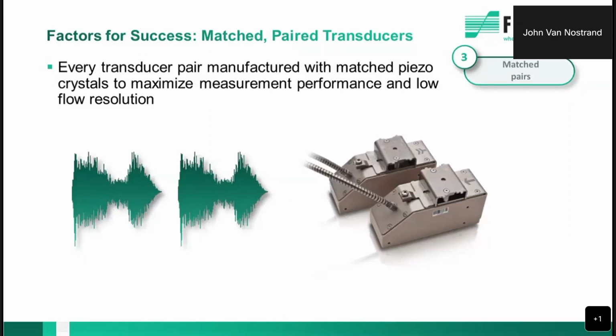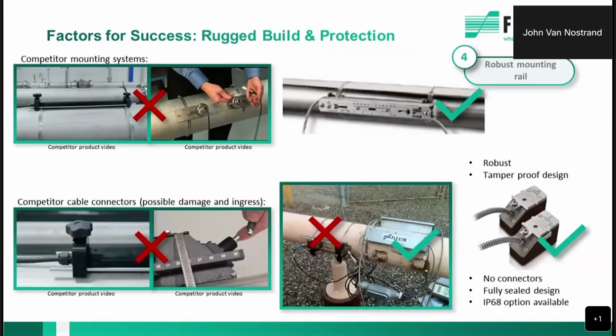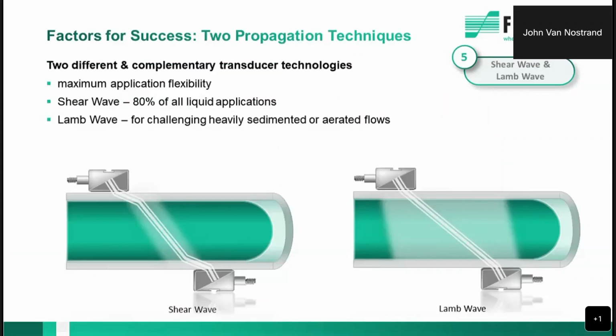I mentioned we match the piezoelectric crystals, and this provides us the tightest accuracy possible before they even go to the calibration rig. This is, again, something that a lot of other manufacturers don't do. We integrate the cables into the mounting, so it's a robust mounting solution, industrial hardened, and it lasts for years. There are, again, no delicate contacts made from the cable to the transducer that could leak. Everything is completely sealed. You can see here on the lower right-hand corner what our transducer cable looks like going into the transducer. Then we also put a mark on the top of them. So when you put those together, you see the arrow goes in the direction of the flow. So there's no guesswork as to which way you install the transducers. You know which is the upstream and which is the downstream.